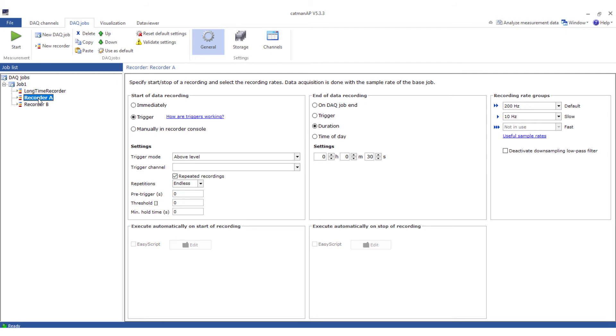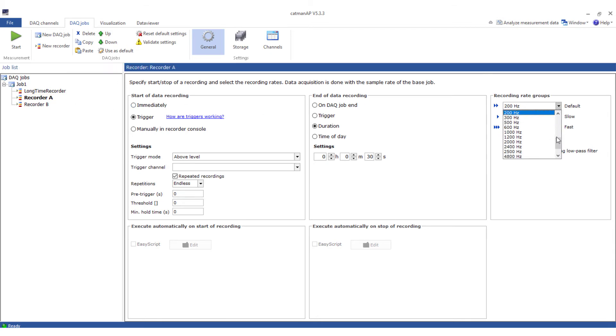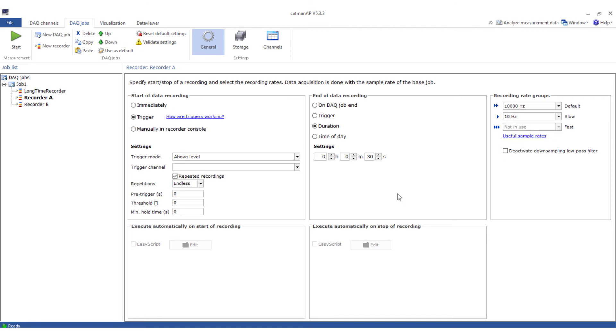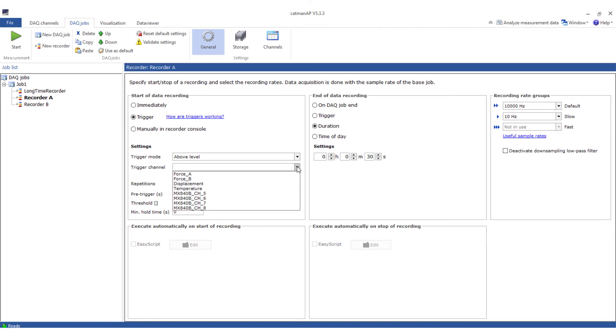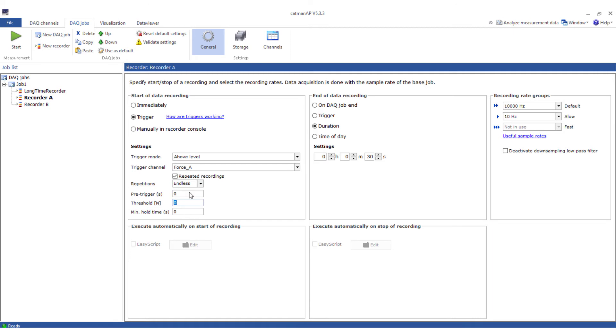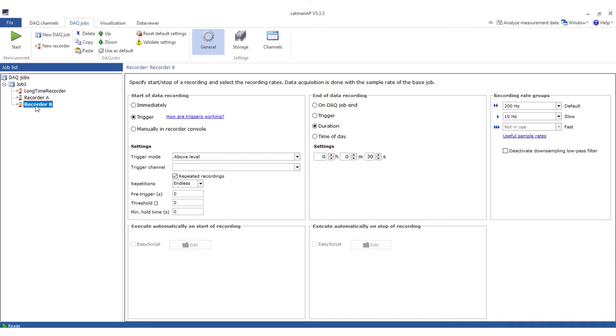We do not want to limit the sample rate here, so we store exactly the same number of values as are measured. The trigger channel of recorder A is force transducer A. I set the level to 5 newton. Pre-trigger 1 second, stop after 4 seconds, so in total 5 seconds.